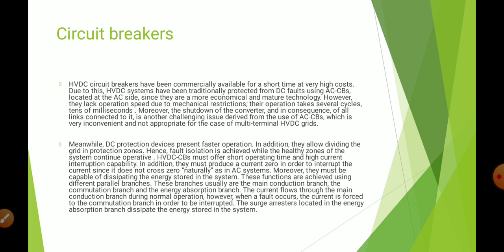Circuit breakers. HVDC circuit breakers have been commercially available for a short time at very high cost. Due to this, HVDC systems have traditionally been protected from DC faults using AC circuit breakers located at the AC side, since they are a more economical and mature technology. However, they lack operation speed due to mechanical restrictions. Their operation takes several cycles, tens of milliseconds, but here the operating speed must be nearly 10 milliseconds, not more than that. So, this is the major challenge in an HVDC system. Moreover, the shutdown of the converter and the consequent loss of all links connected to it is another challenging issue derived from the use of AC circuit breakers, which is very inconvenient and inappropriate for the case of multi-terminal HVDC grids.